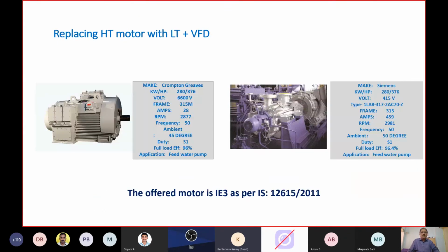I have just given you one case example here, where in order to improve energy efficiency, a sugar factory adopted HT to LT conversion for their boiler feed water pump so that they can use a VFD. Now, high voltage VFDs are very expensive, whereas low voltage VFDs are cheaper. So they decided to convert the HT motor to an LT motor so that they can easily adopt a VFD for energy saving, after having observed that they were using an output valve for throttling the flow.